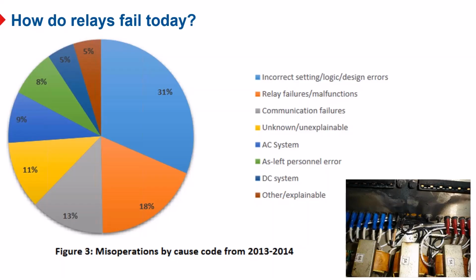So this misoperation study has really driven some of the changes to PRC-005. The picture down on the lower right was an open CT circuit failure in a protective relay that I went to investigate many years ago, actually. The fault wasn't actually at the relay where the arcing occurred. This was a generator relay, and they had done some maintenance on the excitation system. The excitation system shared a set of CTs with this particular relay. When they concluded their testing, they re-landed the wires off by one position on the terminal block. They restarted the machine, flashed the field, put some load on, and the weakest point in the circuit was where the CT signal goes through the aluminum case.